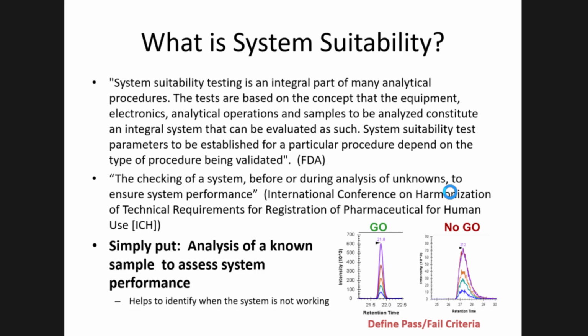And so this is meant for illustrative purposes, but it is real data. When we first started our CPTAC studies, not every lab was running a system suitability. So when we did our second study, we insisted that everybody should. And here we've got one lab that was running, and all of the transitions overlay, and it looks beautiful, and the peak width seems it's a nice Gaussian shape.